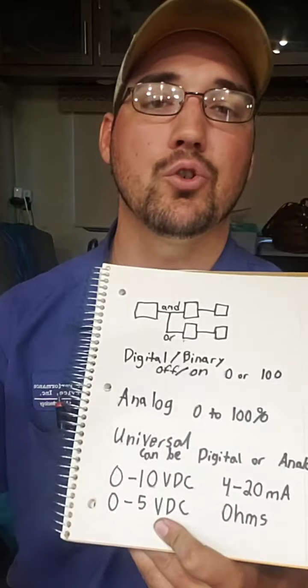A lot of times the 0 to 5 is most frequently seen in actual sensors such as transducers. Transducers use 0 to 5 volts DC for their signal. They have to have 5 volts DC going to them, and then depending on what pressure they're reading, whether it's air pressure or refrigerant pressure, whatever the pressure may be, it's going to output that 0 to 5 accordingly. Then the controller can receive that 0 to 5 back from the transducer to know, okay, this is my pressure. So that's an example of where you'd see a 0 to 5.